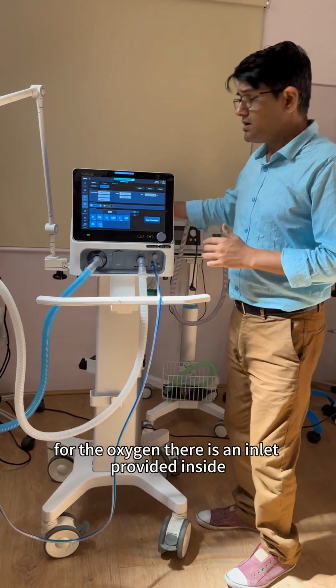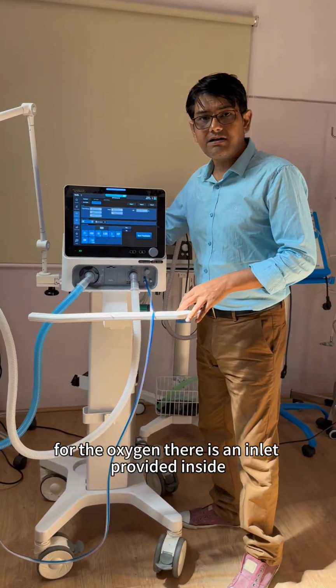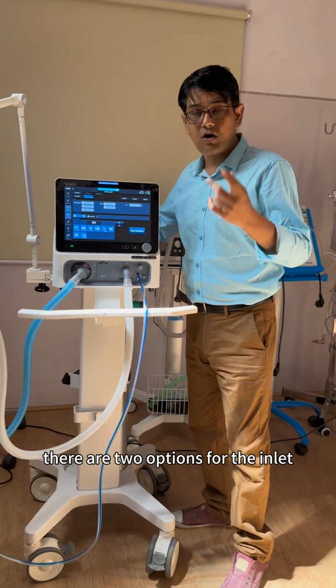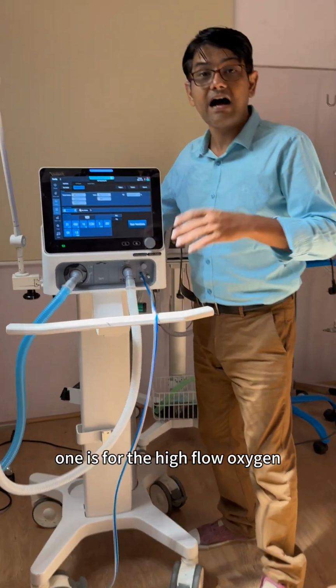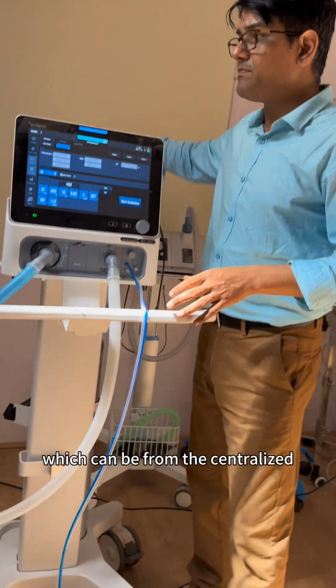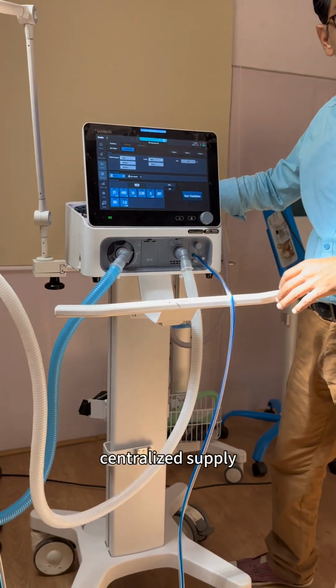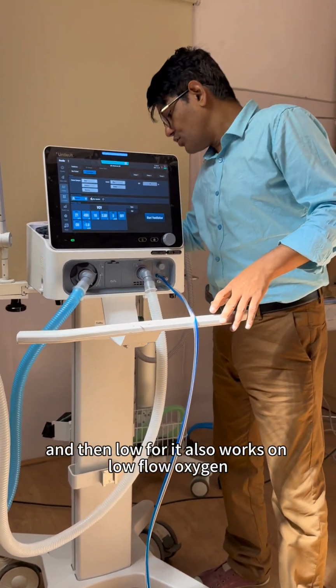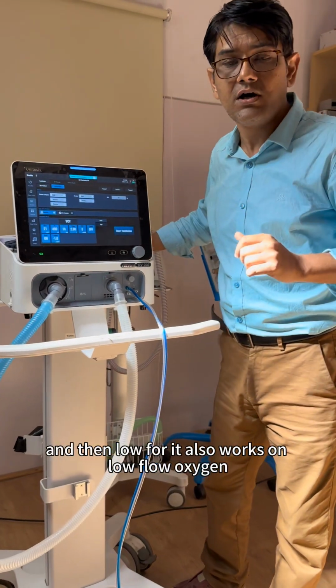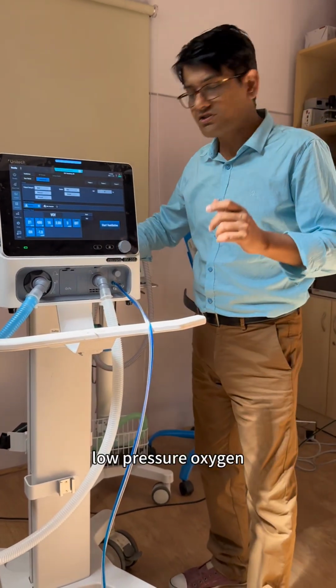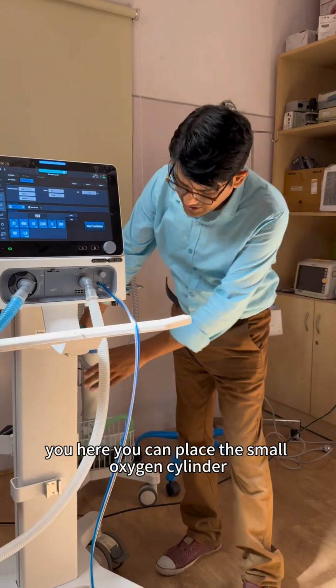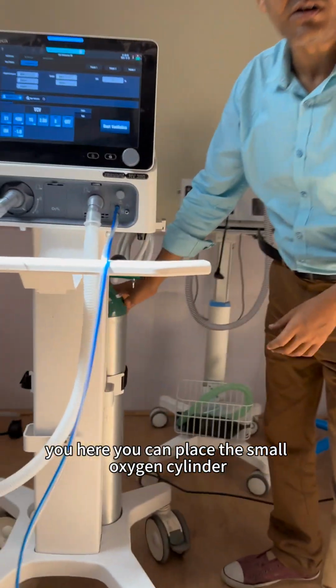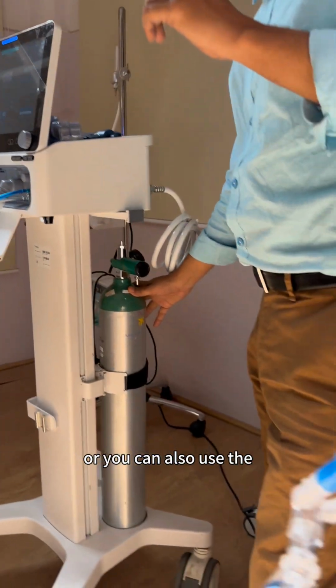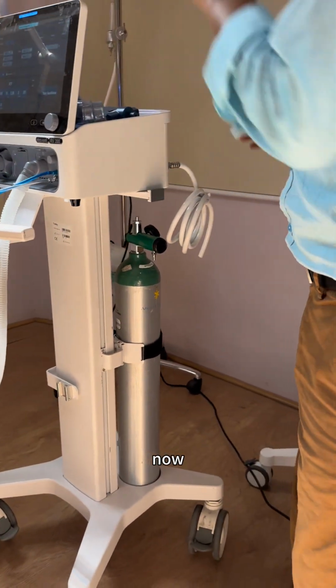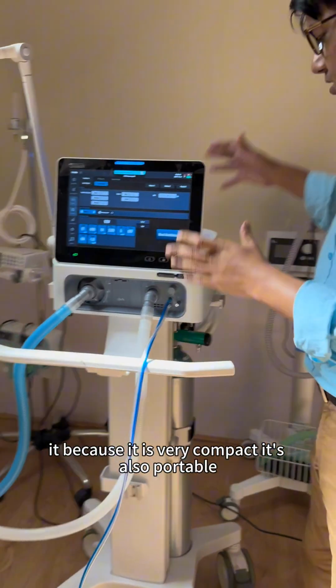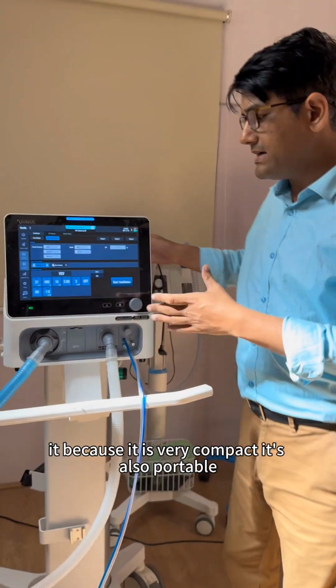For the oxygen, there is an inlet provided inside. There are two options for the inlets. One is for the high flow oxygen, which can be from the centralized supply, and then low flow. It also works on low flow, low pressure oxygen, where you can place a small oxygen cylinder, or you can also use an oxygen concentrator. Now, because it is very compact, it's also portable.